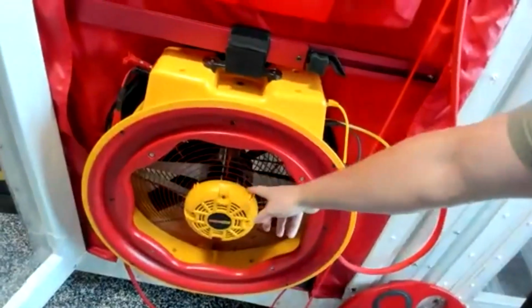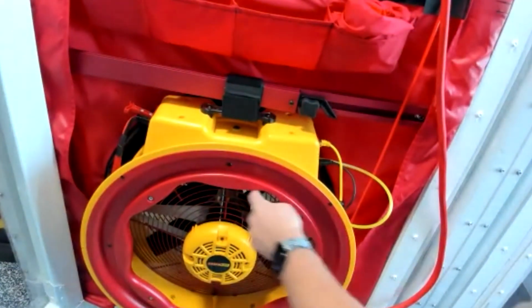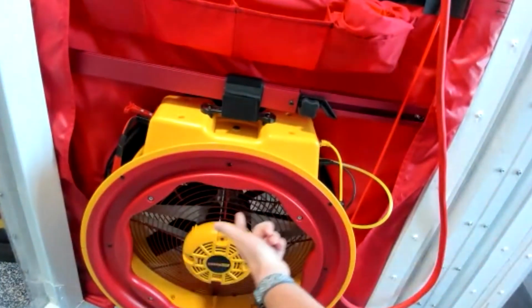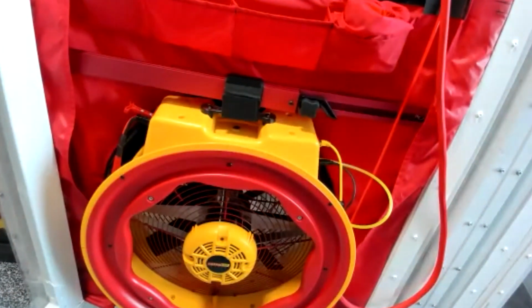If we know fan pressure, which we do because we're collecting it here, and we know the area of the hole in the inlet side of the fan, which is programmed into the manometer, then we can calculate flow, and the manometer does it all for us. Back in the day, we had to do this by hand. There's a lot of math using the old school magnehelic gauges.